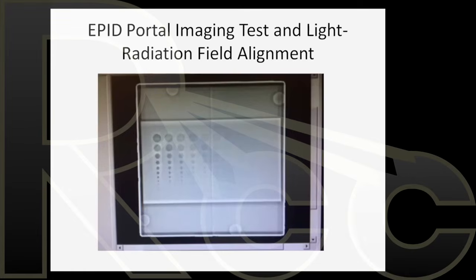If you're doing MV imaging and you want to check the quality of the image, objects are visible inside using MV to see if you can detect the low density object and at least have some sense that the portal imager is working correctly. Here is another device. It's an aluminum plate with many, many holes drilled into it. The holes go from very deep to very shallow, and the holes vary in diameter. So you can test to see the limits of your portal imager. When I run this test, I use it on the portal imager and I put some coins along each side. So I can also check the light field, radiation field edge at the same time using coins, and I can check the quality of the portal imager.